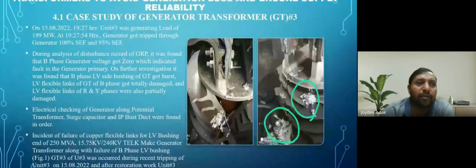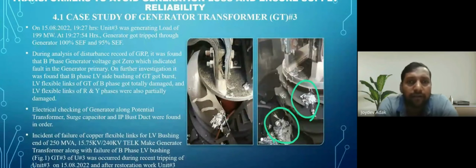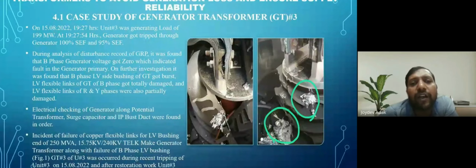So now coming to another case of a transformer. This is the case of GT3 that occurred in 2022. During the fault in the stator, the protections that operated were the 100% stator earth fault and the 95% stator earth fault. These two types of protection acted. This means there is an earth fault in the system. Due to that, this is the picture of the LV bushing. That fault led to the failure or bursting of the LV bushing.